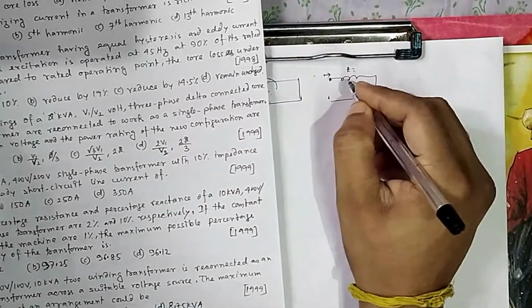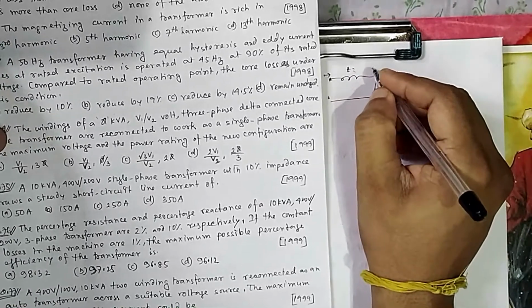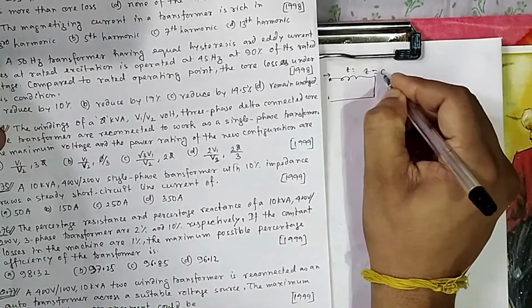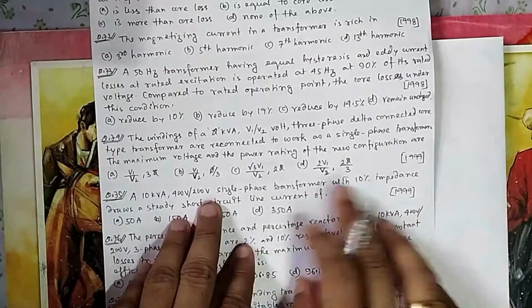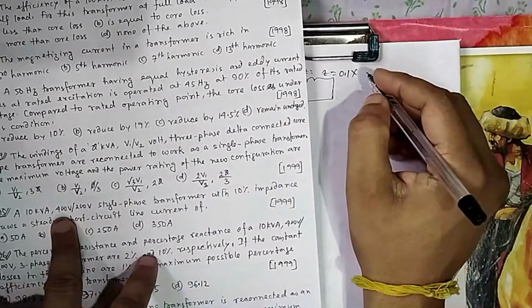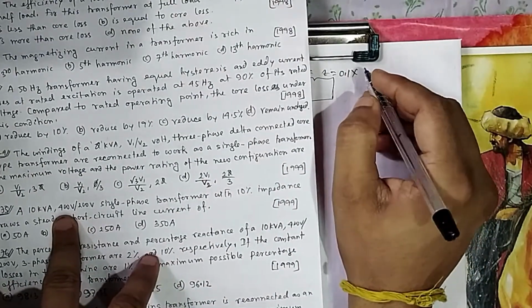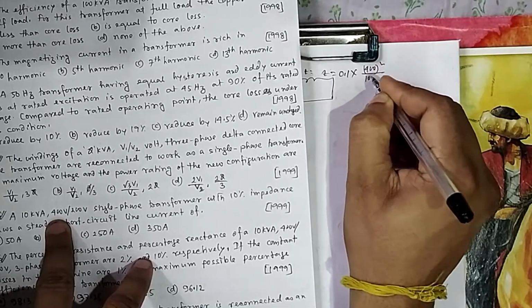What should be the current it is taking? This Z is referred to the primary side. What will be the actual value of this Z? It will be equal to 10%, that is 0.1, or 10 by 100, multiplied by the base Z. If referring to the primary side, base Z is kV squared by MVA, that is 400 volt squared divided by 10 into 10 to the power 3, which equals 1.6 ohm.